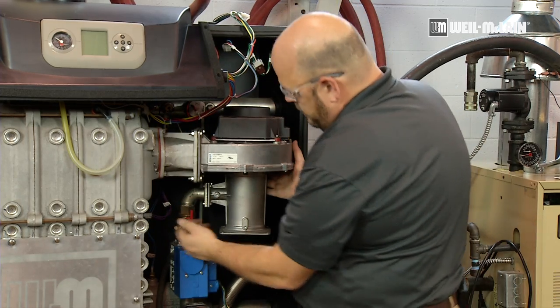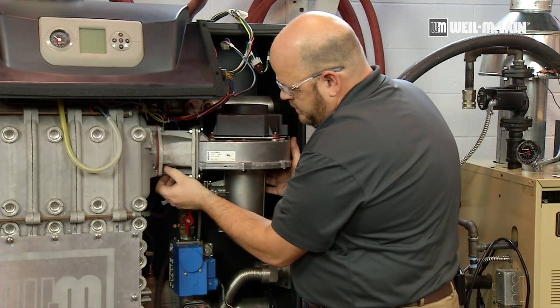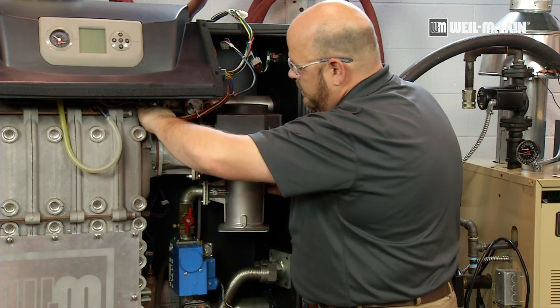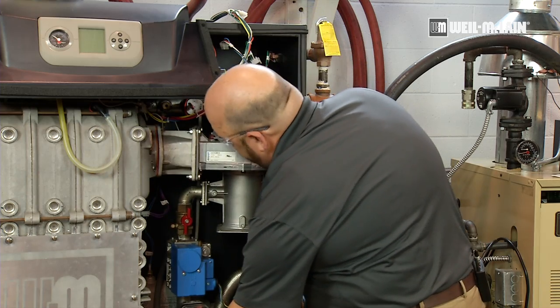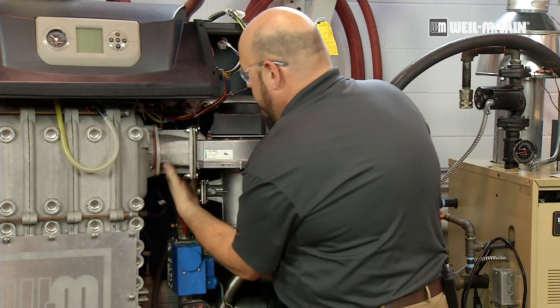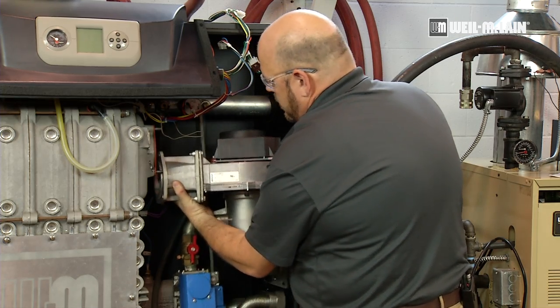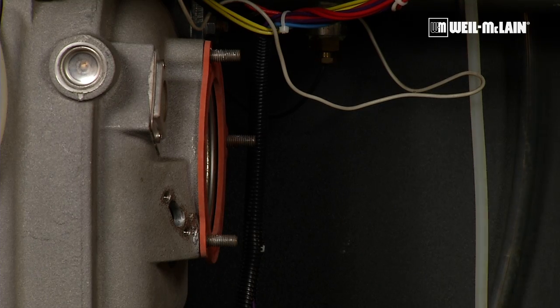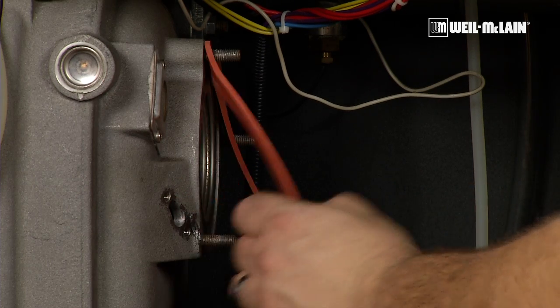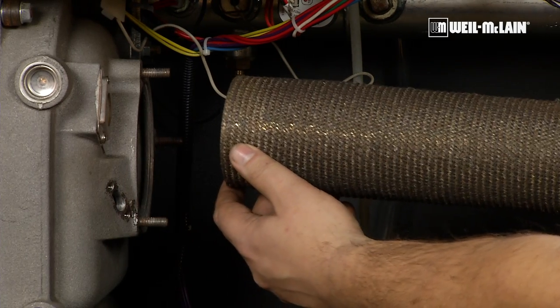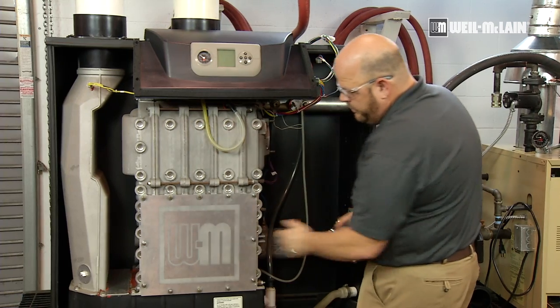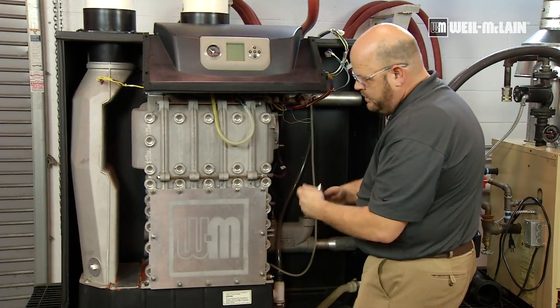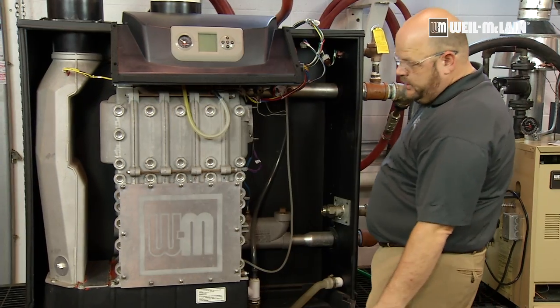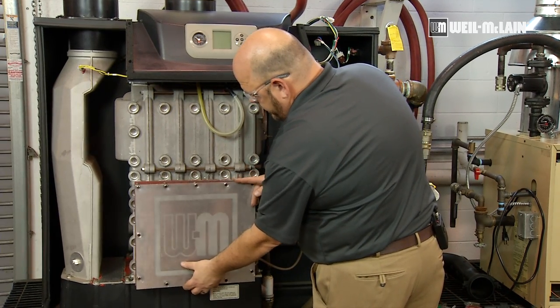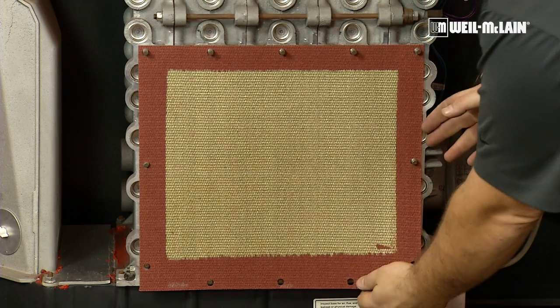With those three loose, you can support the back of the blower with your hand. Take the bottom nut off, the top nut off, and your back nut off, and pull the assembly out. With that out of the way, now we have the burner gasket and our burners inside the boiler, which we can put in our hand, extend your fingers, and pull directly from the unit. Now we need to remove the cover plate and the 13mm nuts around the cover plate. And with all the nuts off, we can remove the cover plate assembly and the cover plate insulation.